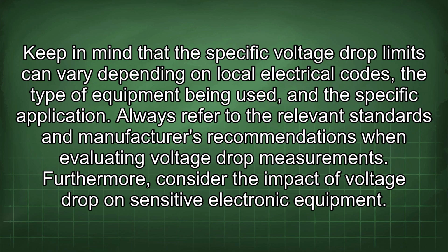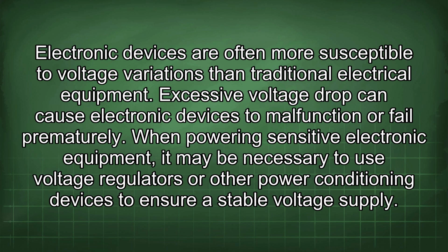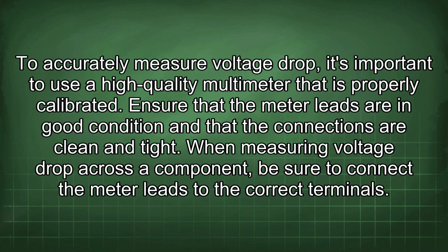Furthermore, consider the impact of voltage drop on sensitive electronic equipment. Electronic devices are often more susceptible to voltage variations than traditional electrical equipment. Excessive voltage drop can cause electronic devices to malfunction or fail prematurely. When powering sensitive electronic equipment, it may be necessary to use voltage regulators or other power conditioning devices to ensure a stable voltage supply.